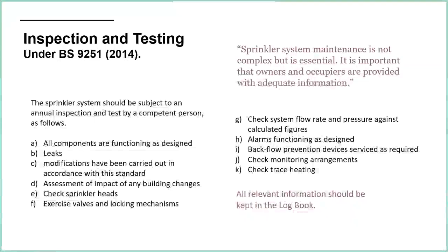B, check for leaks. C, check for any modifications of either the building or the sprinkler system or both, just to make sure that everything is still in full compliance. Assessment of impact of any building changes. So has there been an extension? Have they changed the use of one of the buildings? Is one of the buildings now suddenly a games room or a laundry room or a conference room or a cafe? What have they done to the building which may affect the sprinklers?